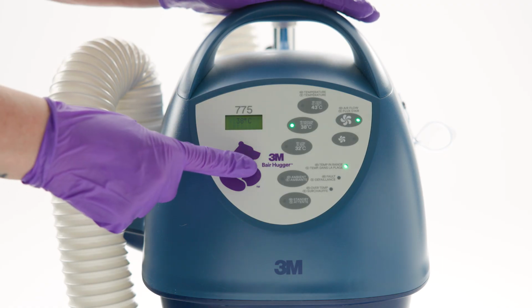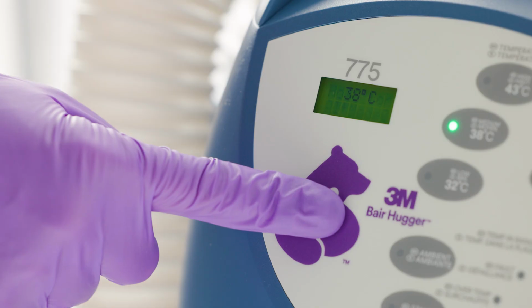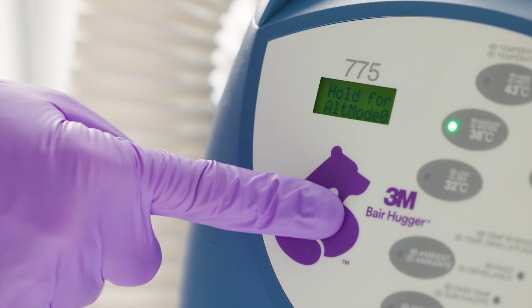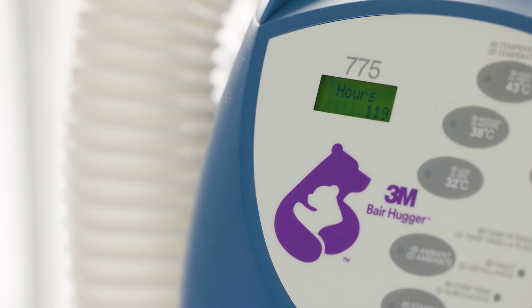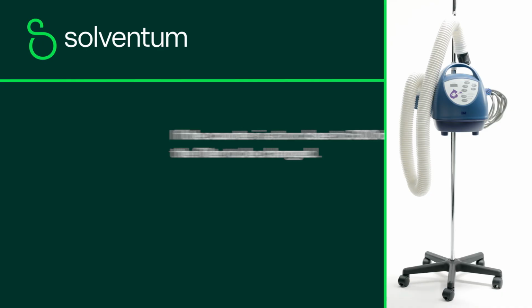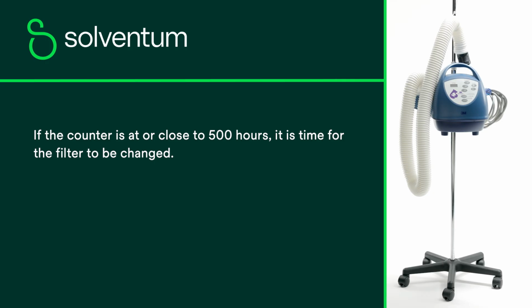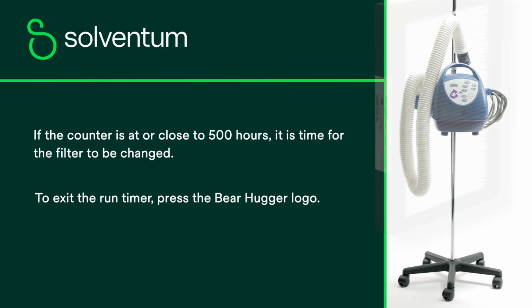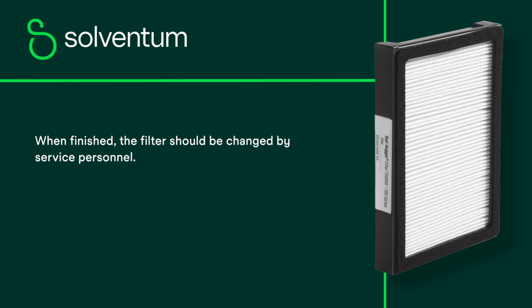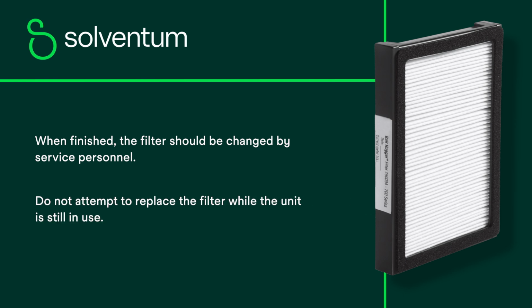To check the filter usage time, press and hold the Bair Hugger logo for 3 seconds. The run timer will appear on the display showing the use in hours. If the counter is at or close to 500 hours, it is time for the filter to be changed. To exit the run timer, press the Bair Hugger logo or wait 60 seconds. When finished, the filter should be changed by service personnel. Do not attempt to replace the filter while the unit is still in use.